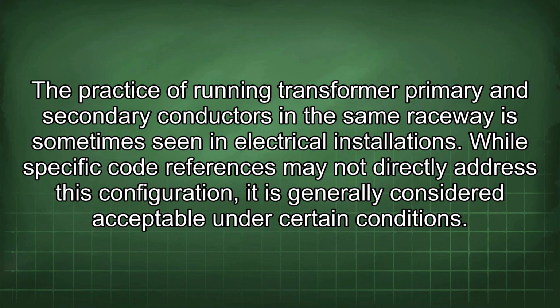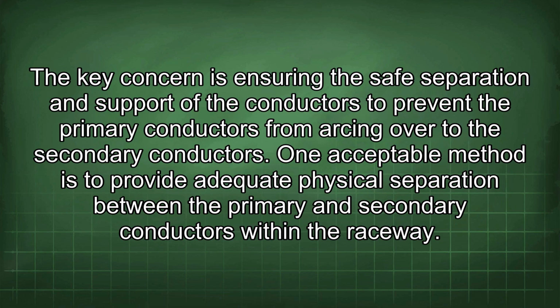The practice of running transformer primary and secondary conductors in the same raceway is sometimes seen in electrical installations. While specific code references may not directly address this configuration, it is generally considered acceptable under certain conditions. The key concern is ensuring the safe separation and support of the conductors to prevent the primary conductors from arcing over to the secondary conductors.